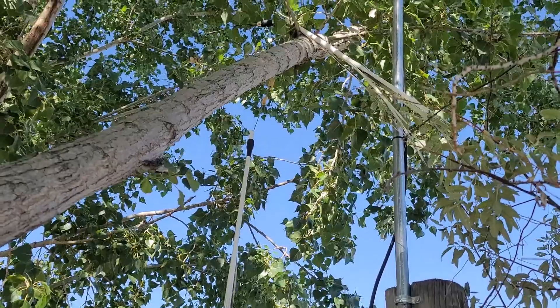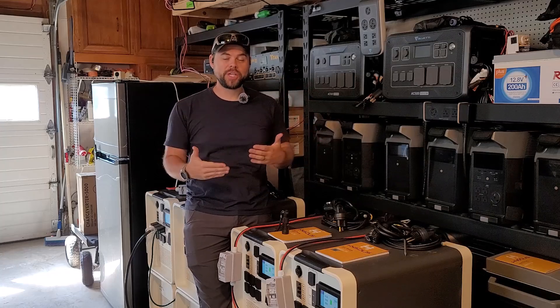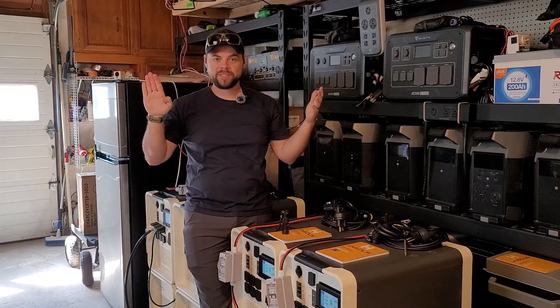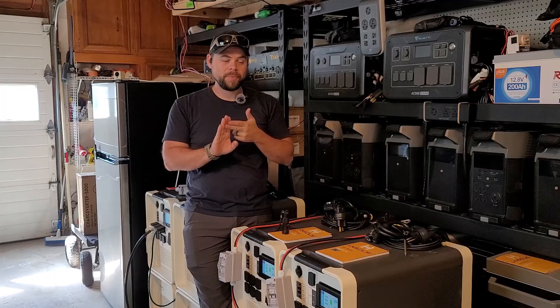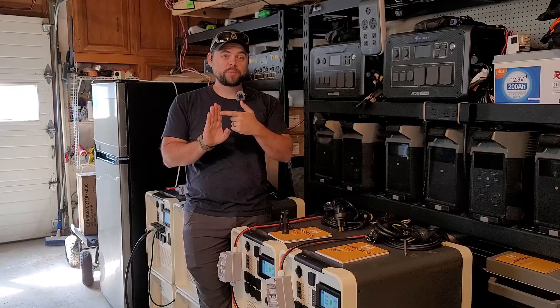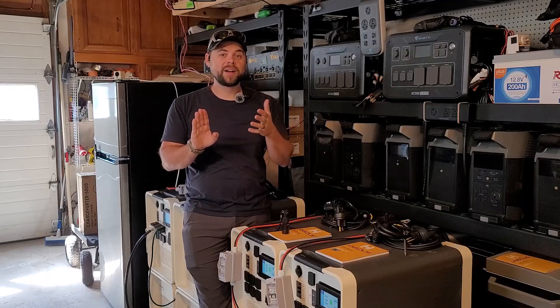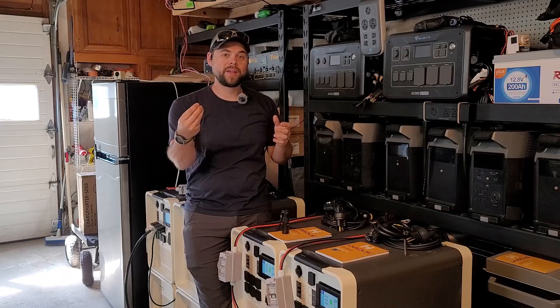Just to give you a closer look — you can see it's hanging in the tree in two huge chunks. Now when it comes to EMP protection, I have an EMP shield on my main electrical panel. But this is where I found the chink in my armor — why I was susceptible to this lightning/EMP strike. I have my main electrical panel with the grid coming in, which runs the whole house. Off of the main panel I have a sub panel in our basement, and the well pump is on that sub panel. The well is outside with wires going straight to the sub panel — it's the first breaker in that breaker panel. So the path goes from the well pump up the casing, through the ground, into the breaker, and then to the control board.